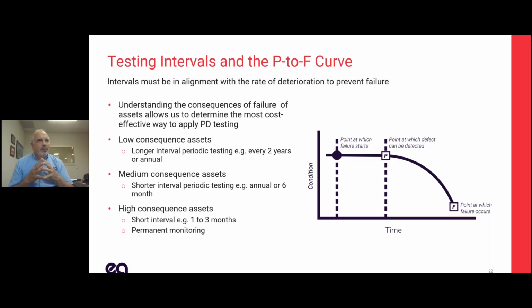The question we get asked all the time is, okay, I've got partial discharge, how long do I have before this cable fails? Anybody that can predict that is a better man than I. It's impossible to predict. It varies every time. But you want to have some idea. There is a point at which the failure starts that's not detectable. Sometime later, that failure becomes detectable. And at some point after that, it's going to cause a catastrophic failure. Sometimes that's minutes, sometimes months, sometimes decades. You need to understand the type of failure and the type of discharge you're looking at, and have an idea of how fast those typically progress.